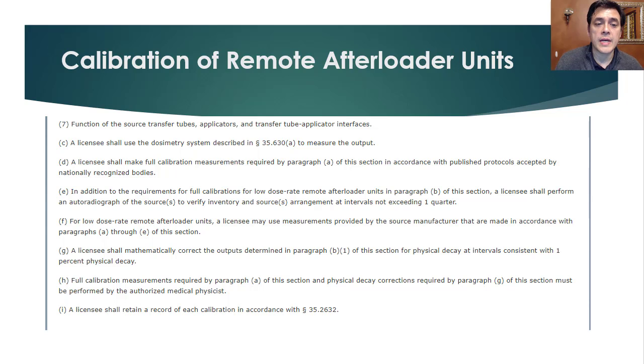The statute goes on to say that the licensee shall use the dosimetry system described in 35.630, which is the calibrated system to measure the output, and a licensee should make full calibration measurements upon the published protocols of a nationally recognized body.